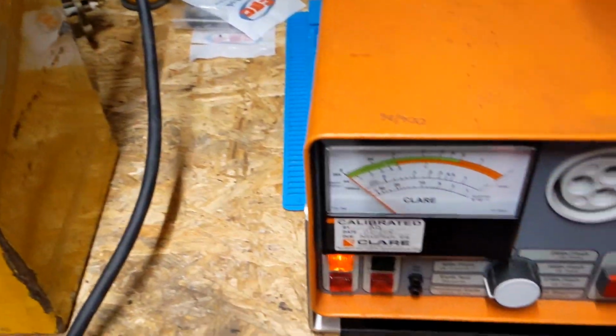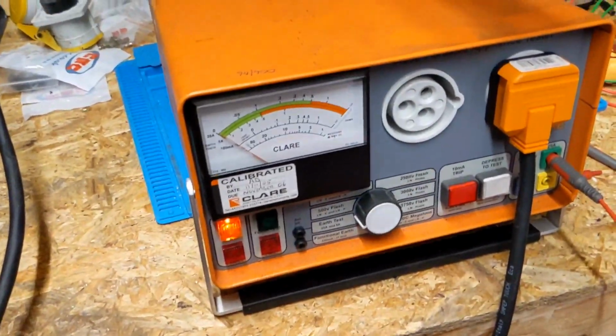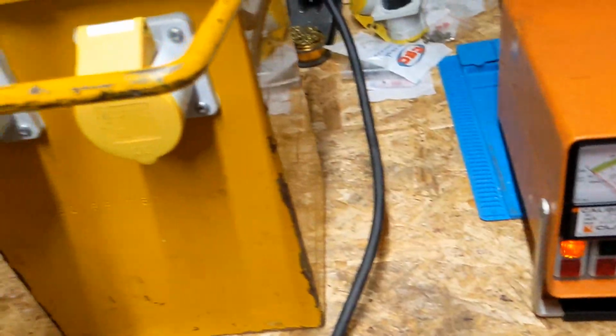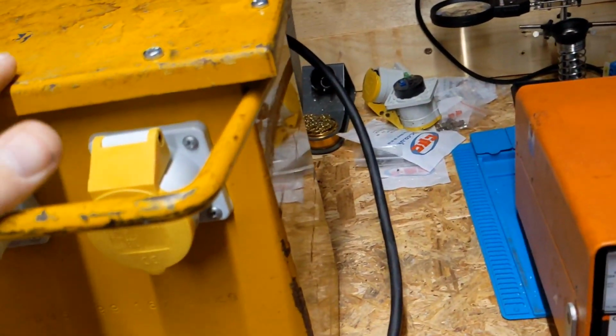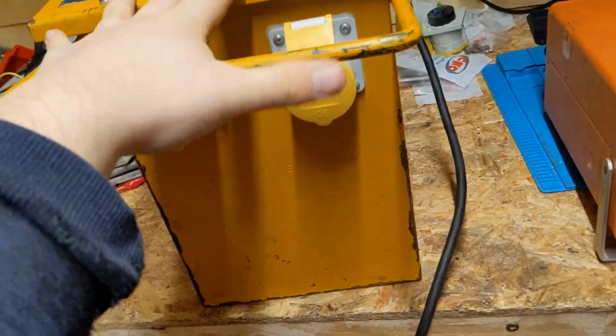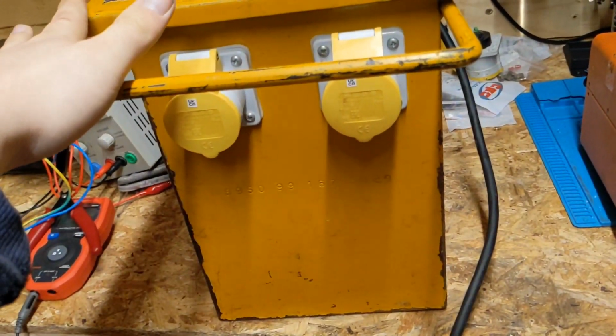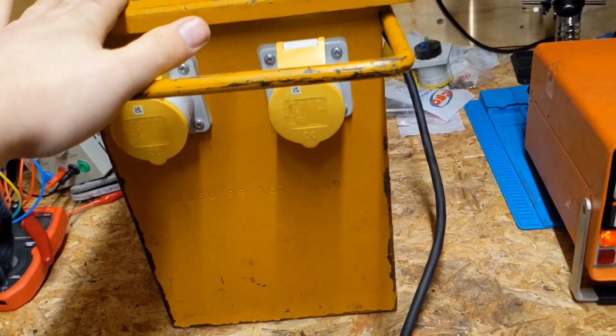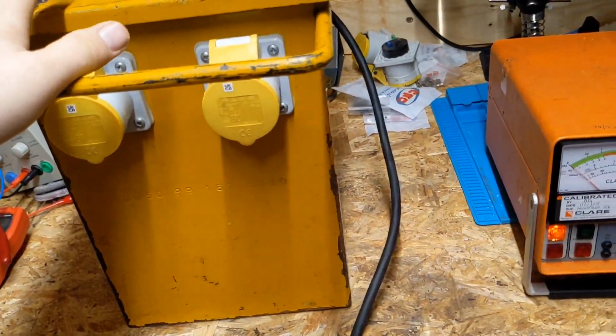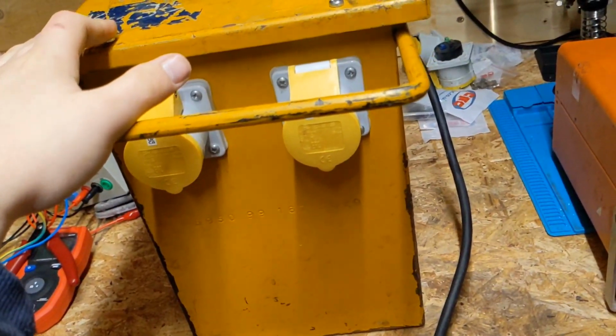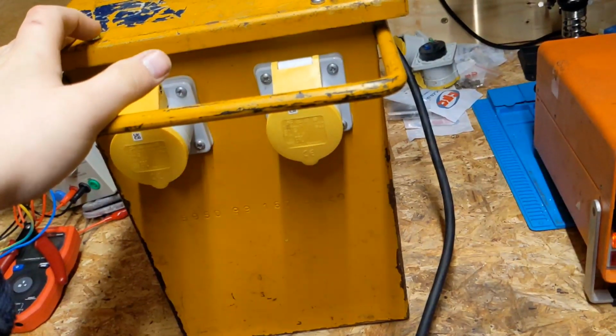So that there has passed the basic checks and is safe to be put into use. What we'll do is tag and ID it so it's identifiable in the future. And since this is actually going out, we'll put 3 months on this because it's all brand new cable and everything - recommend it be retested in 3 months.